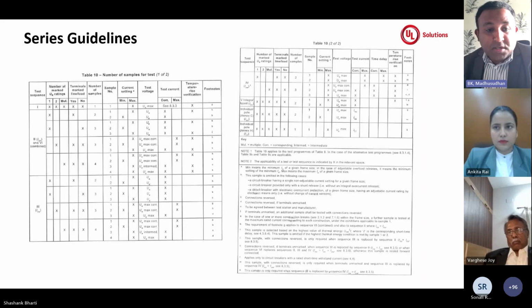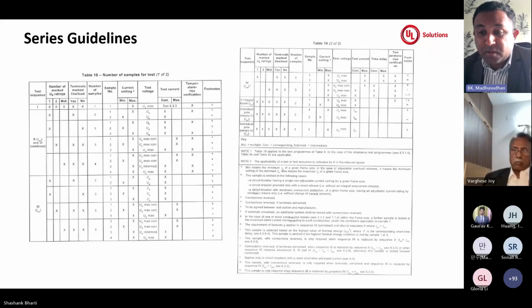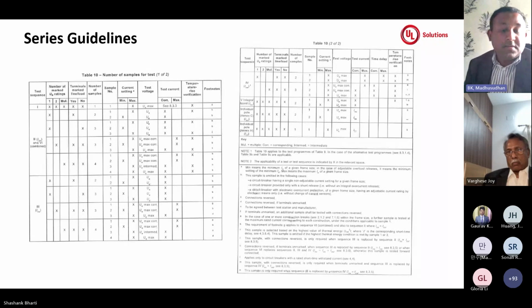And similarly for sequence 2, 3 and other sequences, again the standard is giving a reference table here, from table 10. So we have to pick based on the declaration from the manufacturers, whether it is a multiple voltage rated breaker, or whether it is terminal marked or unmarked, or whether it is a multiple settings breaker. So based on this table selection, we can arrive at a sample plan for the complete sequences for the set of construction breakers that are going to be looked into for testing. Yeah, next slide, please.